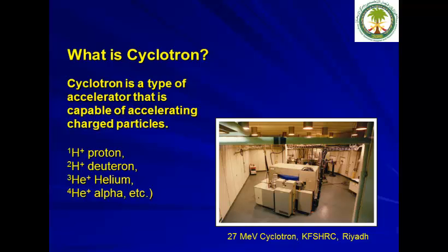So what are cyclotrons? A cyclotron is a type of particle accelerator capable of accelerating charged particles. These charged particles can be protons, deuterons, helium particles, or alpha particles. This is a picture of our cyclotron — a 27 MeV cyclotron installed at King Faisal Hospital in Riyadh in 1979.